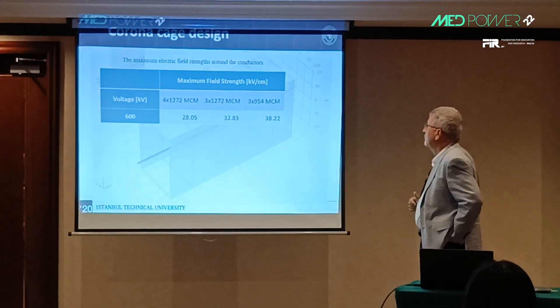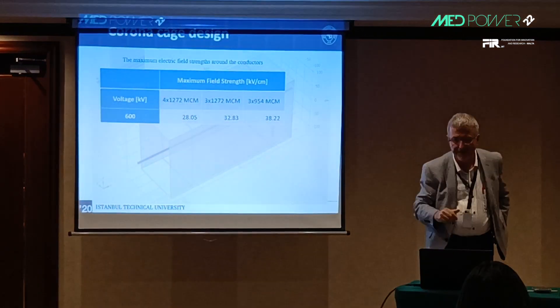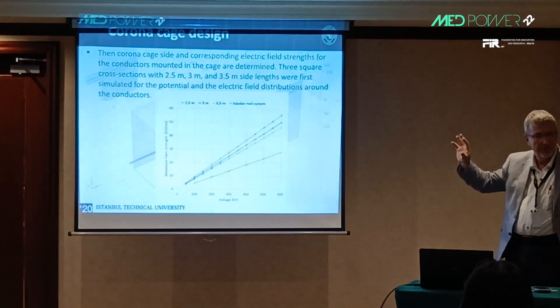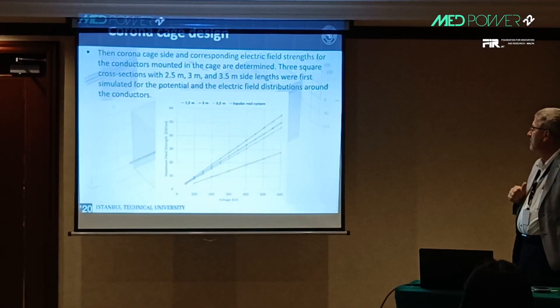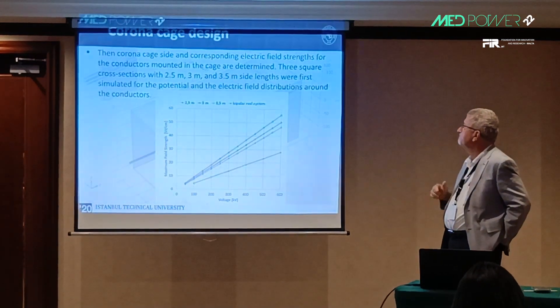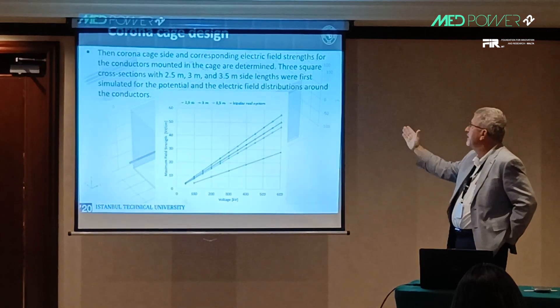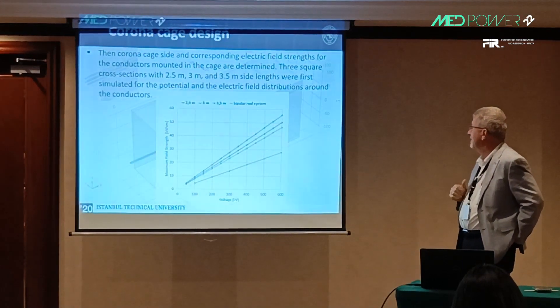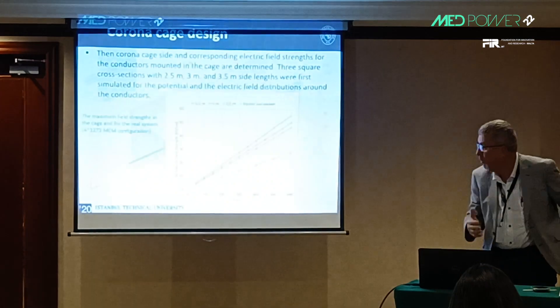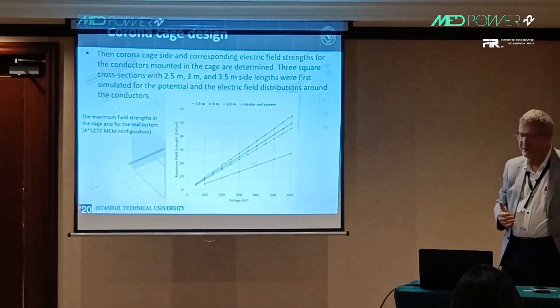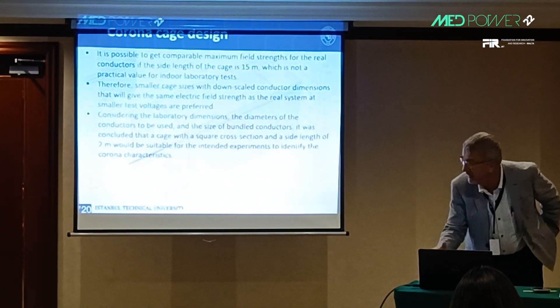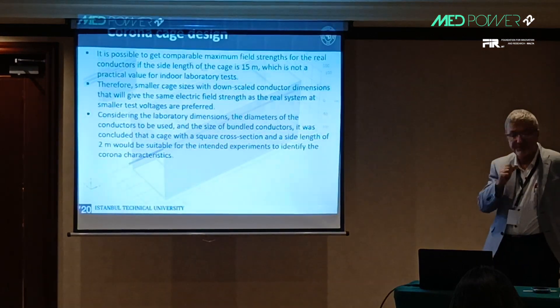We want to keep those field strengths under specific values. At 600 kV of test voltage, the values of maximum field strength are reported here. So we want to design a corona cage whose values will be more or less the same at decreased voltage levels. From this figure, we can understand that it was impossible to obtain identical conditions with a cage less than 15 meters of side length, and that is why we need to use scaled conductors.